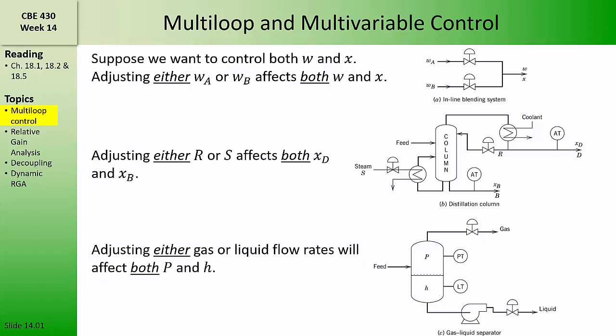Even for very simple operations like this flash drum, if we want to control both the pressure in the tank and the level in the tank, we can adjust the gas flow rate and the liquid effluent flow rate. But adjusting either of those flow rates will affect both the pressure in the tank and the level in the tank.